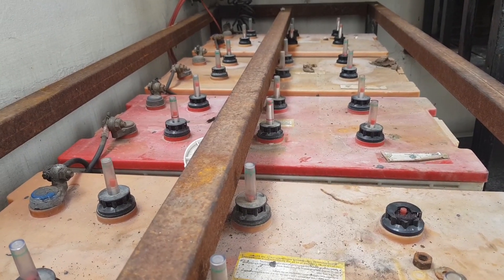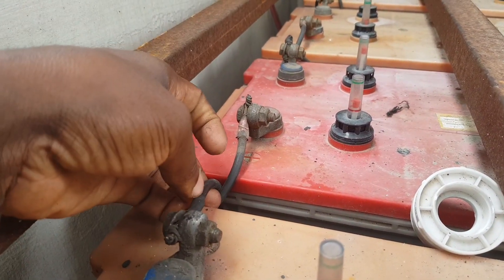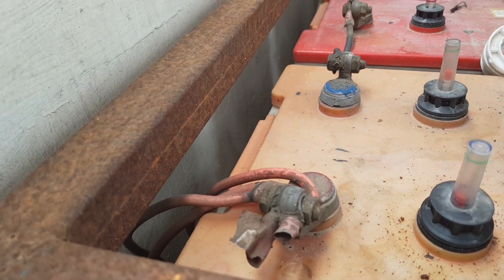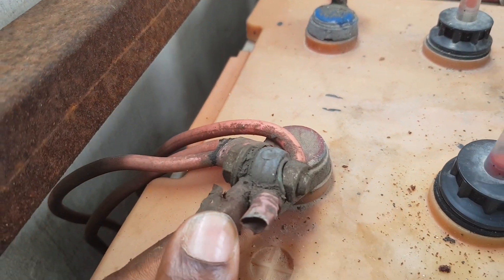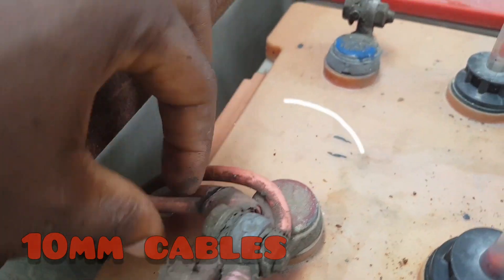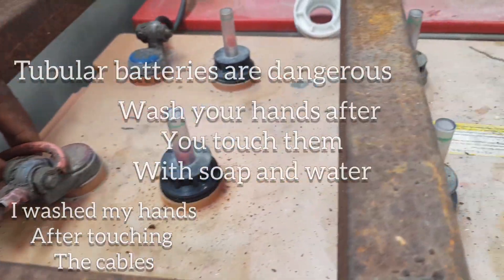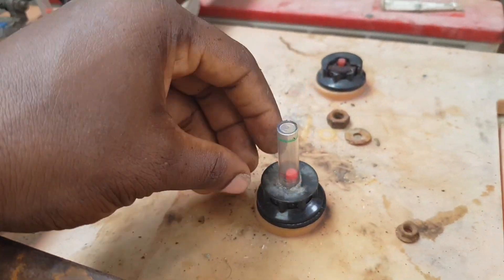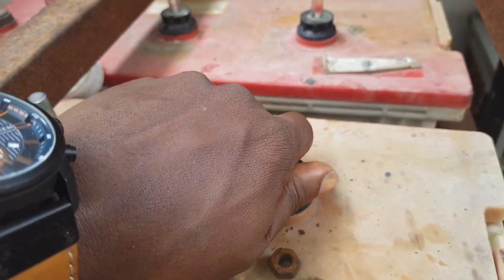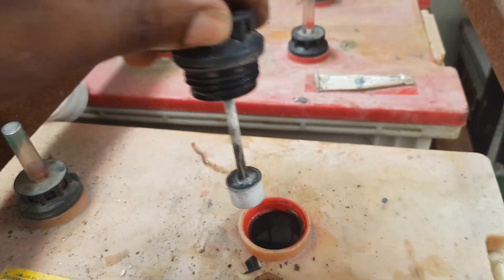I came here this particular day to check out this pretty bad battery. One of the causes that made this battery bad is pretty amazing — I found thin cables like this. How do you actually push energy through something like that? Who makes cables like this for a battery like this? This is a big tubular battery, a 200 amp 12-volt tubular battery.